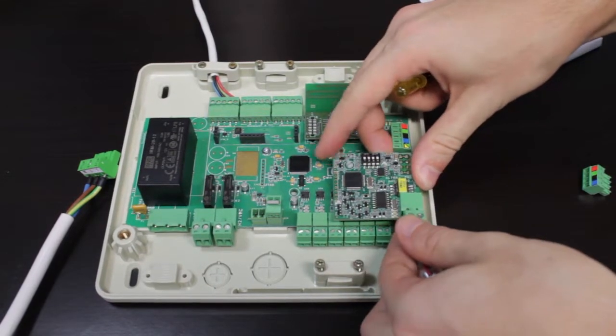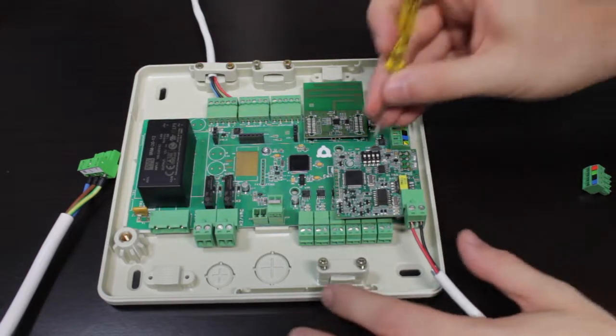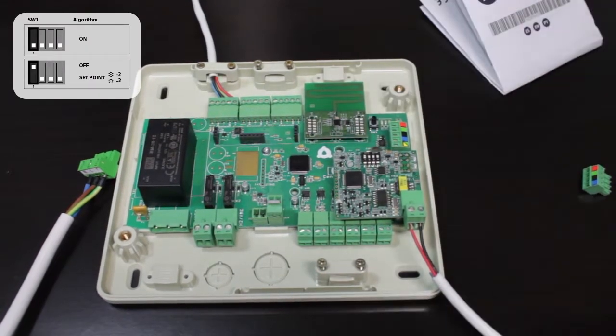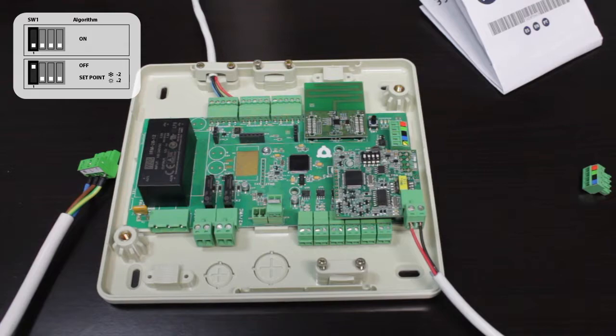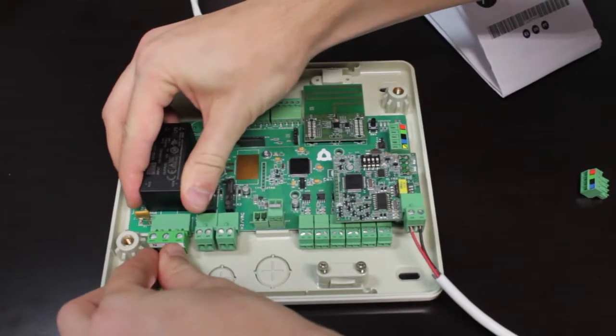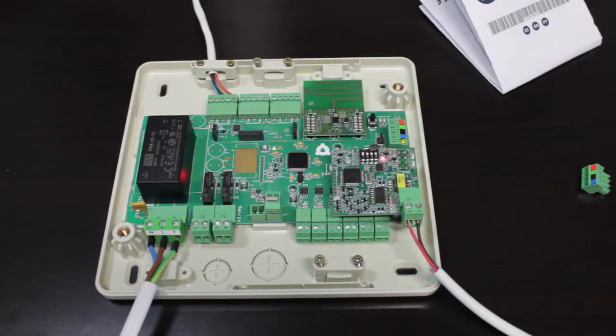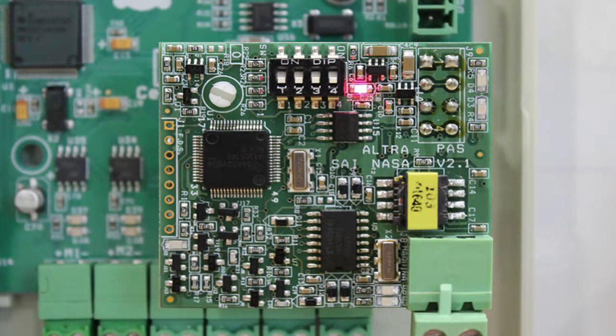Once all the connections are successfully made, configure the micro switch if necessary. Finally, it's time to power up the Airzone system and Samsung AC unit. Check all the status LEDs on the gateway to verify correct operation: power supply LED, microprocessor activity LED, communication LEDs gateway-system, and communication LEDs gateway-AC unit.